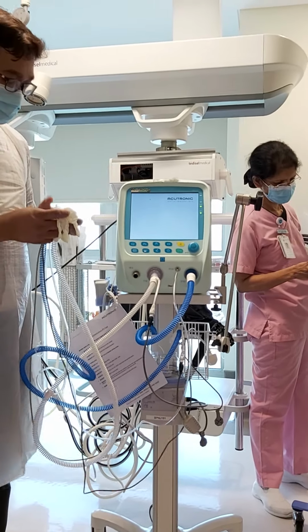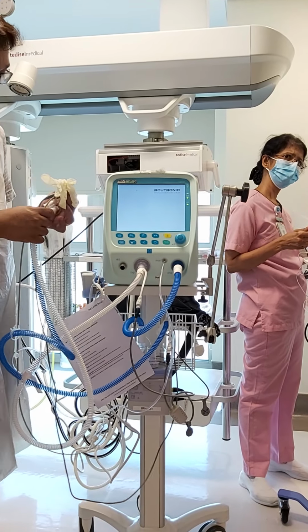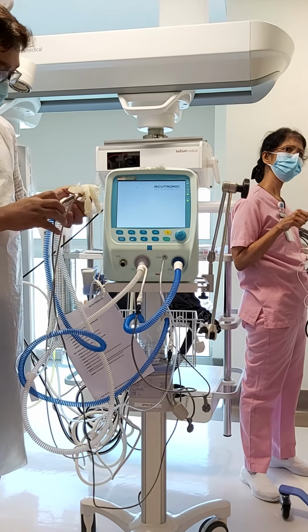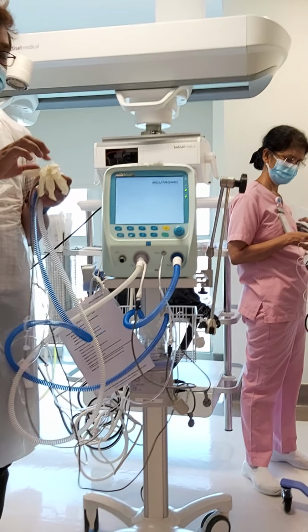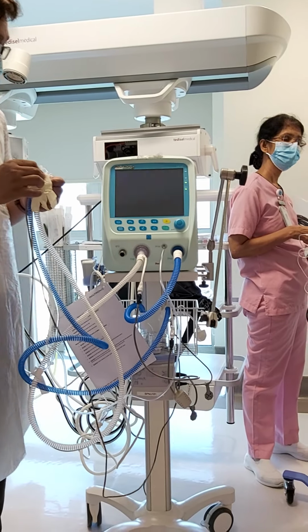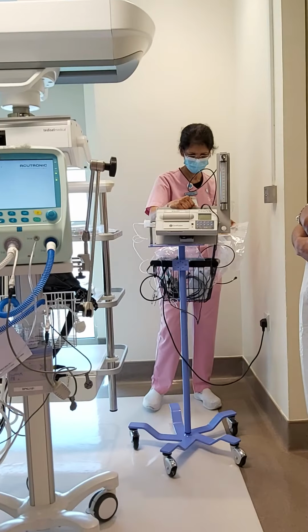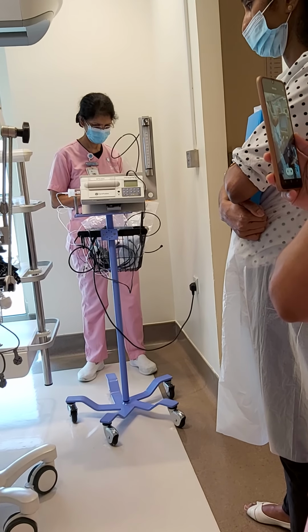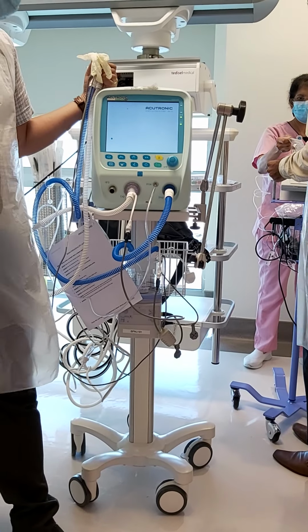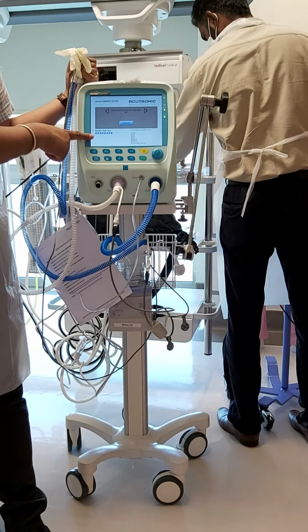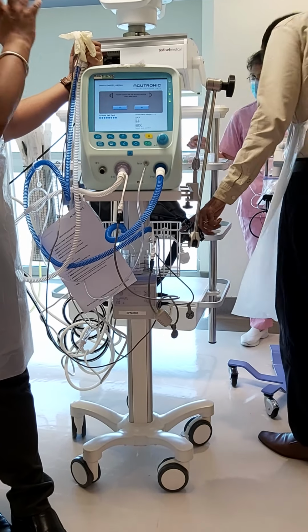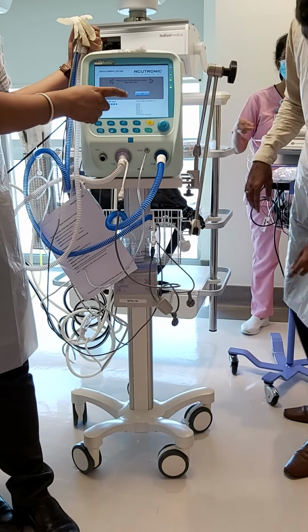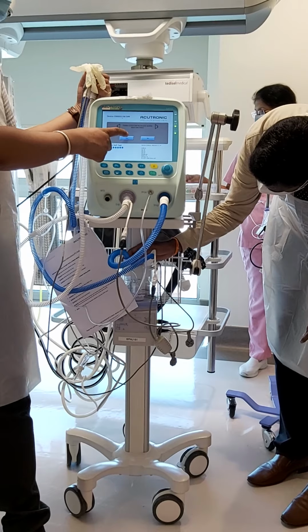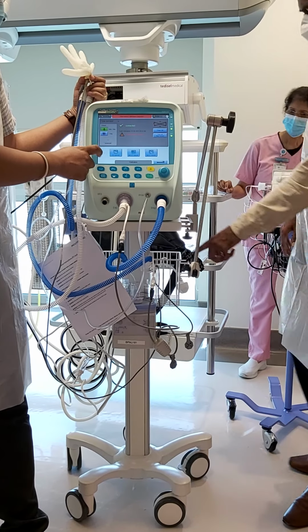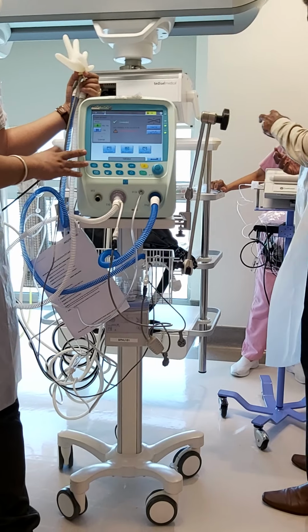Okay, so when you start this machine, you will have to do 2 calibrations. Are you doing this, ma'am? 2 calibrations. What are the 2 calibrations? If you still remember. One is your flow sensor, of course, and the second is oxygen. You're aware, ma'am. No need for training. The first one is the subsystem test, and then it will ask you, do you have an audible alarm? So just press this, you can hear the alarm, so press yes. If you do not, then you can press no. Then you should not use the machine. Okay? If it alarms, then press yes. Then you will be on this. This is your calibration screen. So you have your flow sensor calibration and your oxygen calibration.